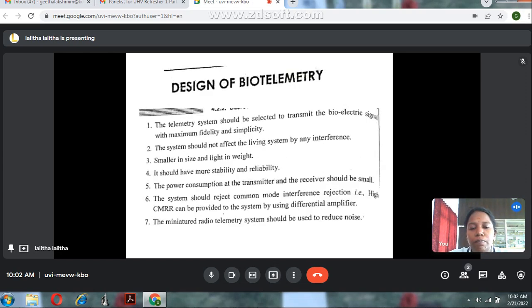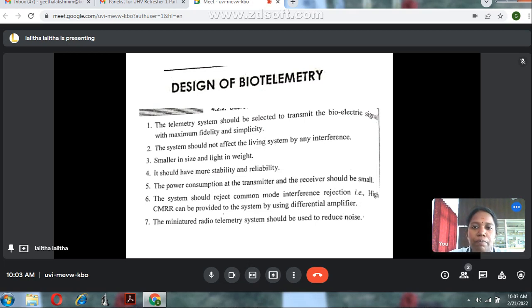Regarding the design of biotelemetry: a telemetry system should be selected to transmit the biological signal with maximum fidelity and simplicity. The system should not affect the living system by any interference — that is, noise or error. The telemetry system should be small in size and light in weight, and should have more stability and reliability.